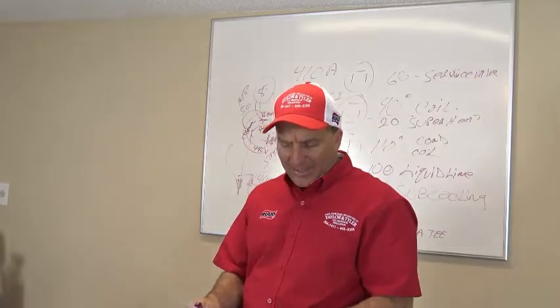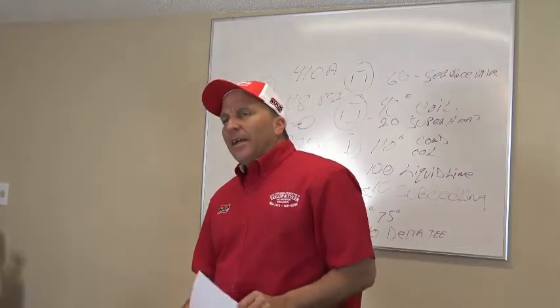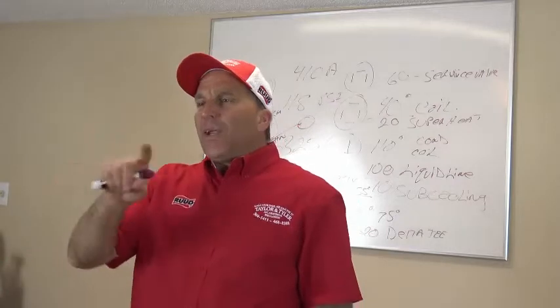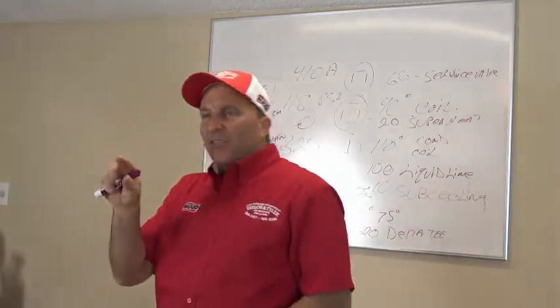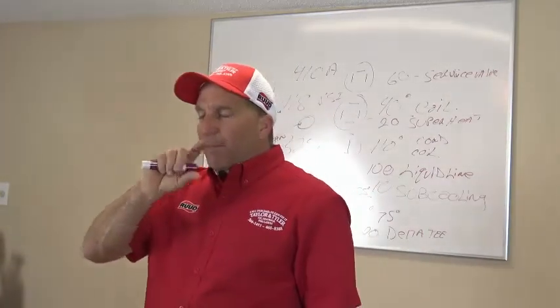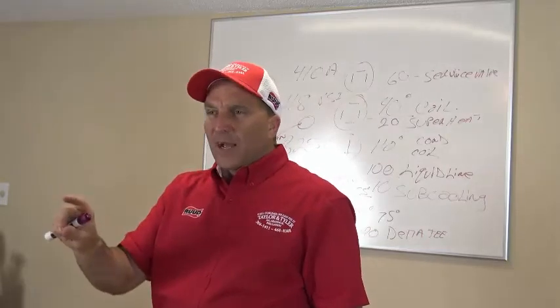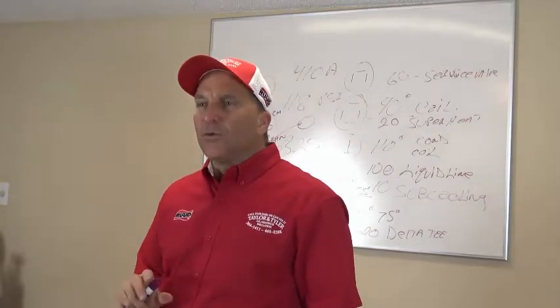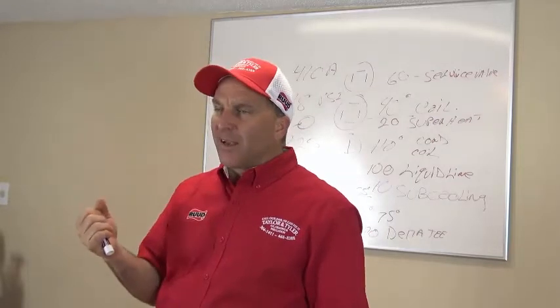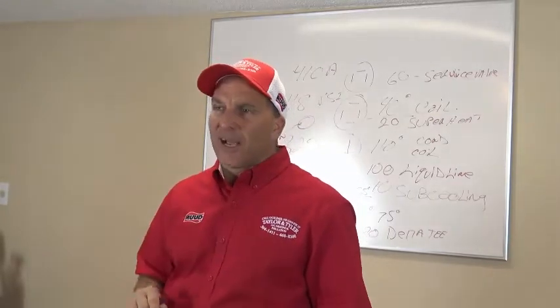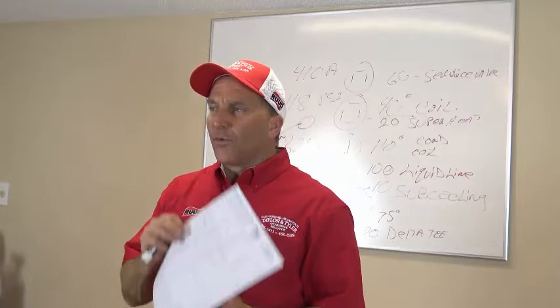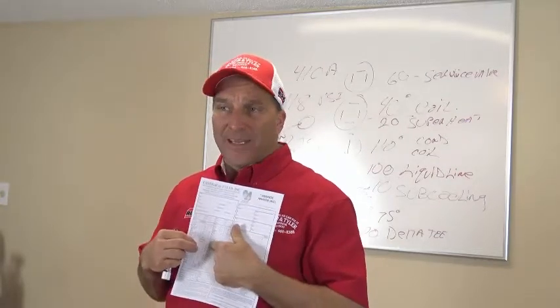Max fuse size and actual fuse size. If you go to your condenser and read the label, it's going to have a max fuse size and minimum fuse size. So you read the max fuse size on there, and then you pull your disconnect out, or look at your breaker and see what size breaker it is. Put your actual fuse size, what is actually in there, on there.